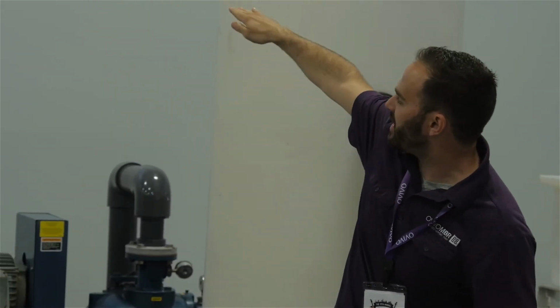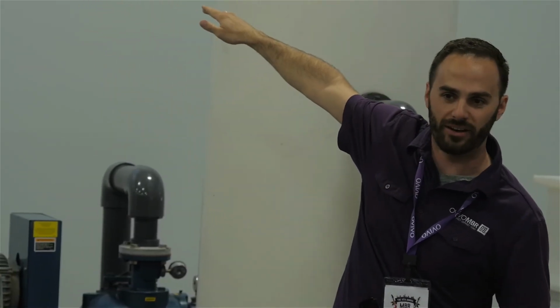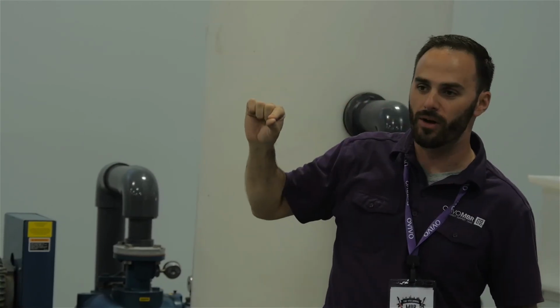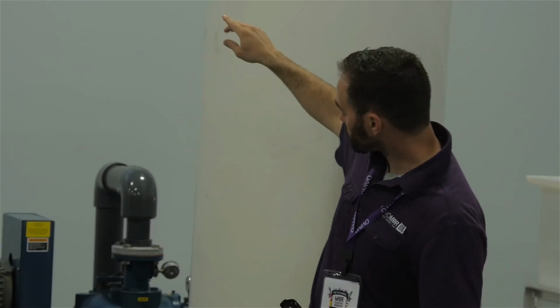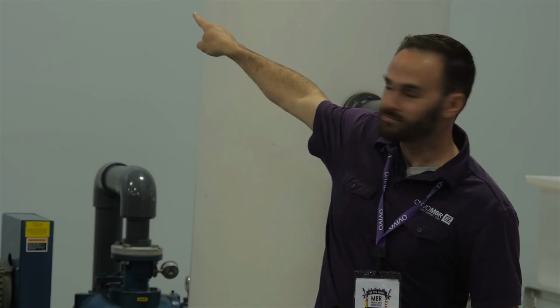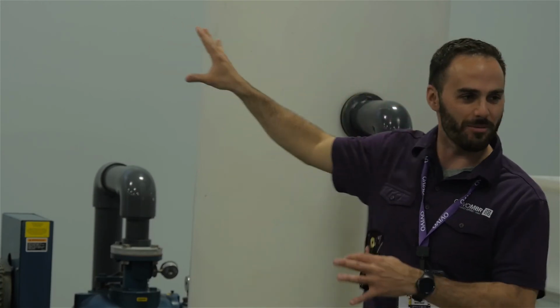What we can also see here is on our permeate flow, we had a nice straight line on the last permeate cycle. We were able to control that flow very, very well. This cycle is starting to look totally different. We need a little bit more time to pass permeate, but you can already see the effect on permeate flow.